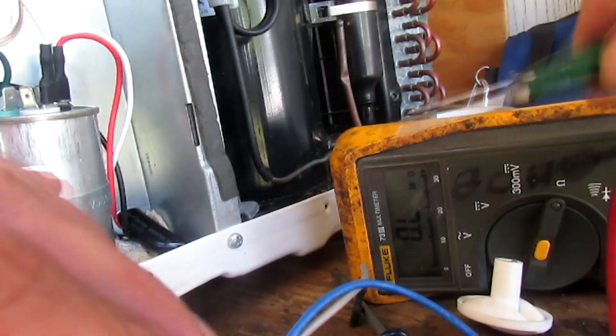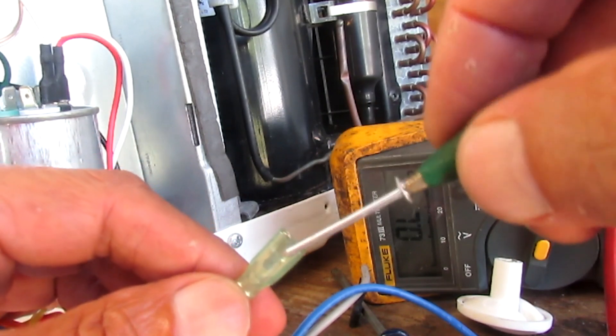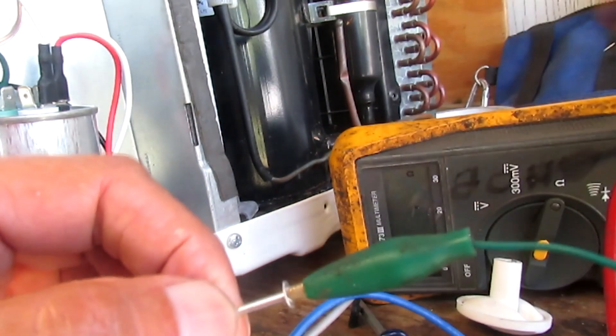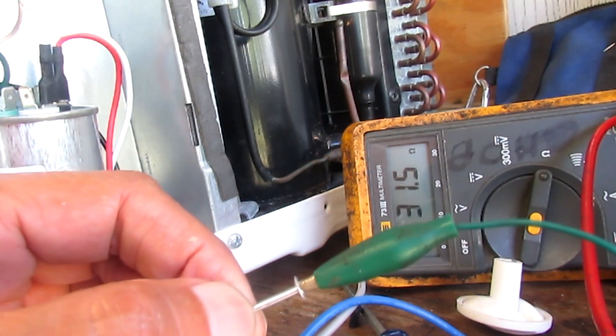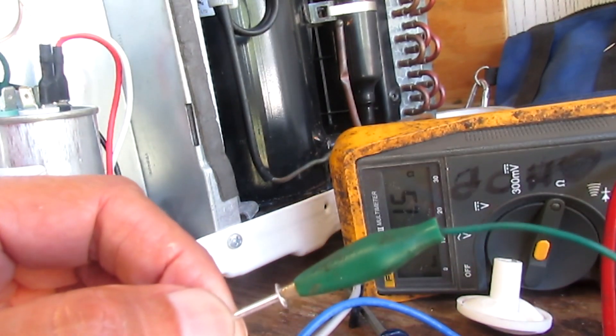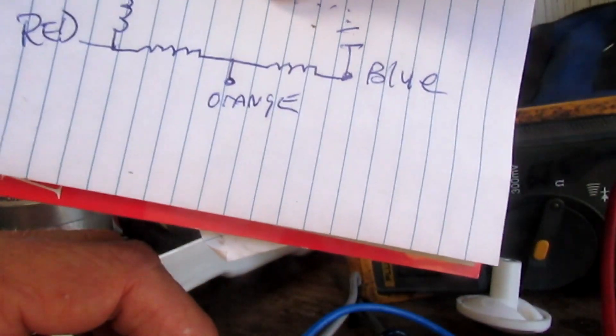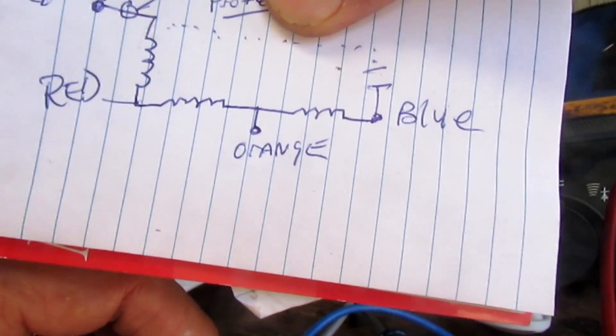So now I'll hook my meter to the blue lead. Now let me check out the orange lead, and there we go. We got 31.5 ohms. So I don't have the specs for this motor, but I'm going to guess that isn't a dead short and it isn't an open. That's the blue to the orange.